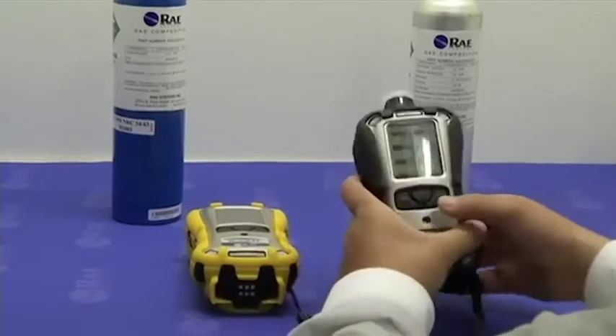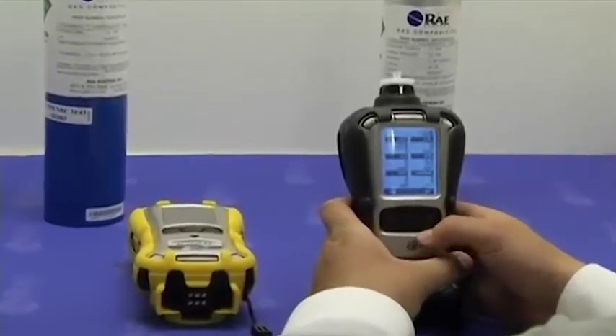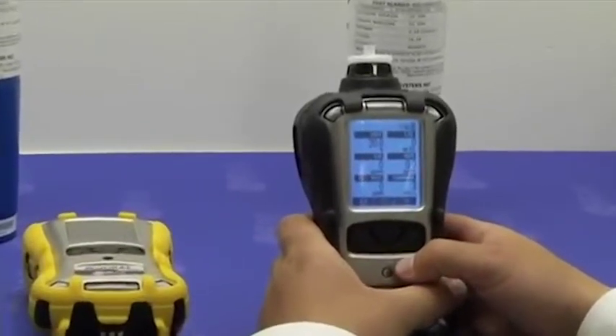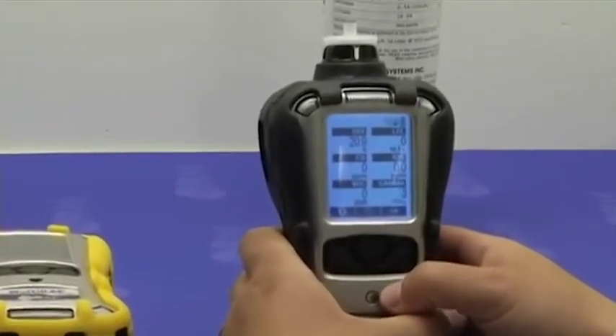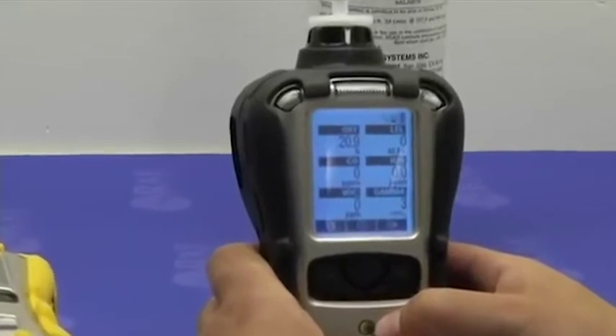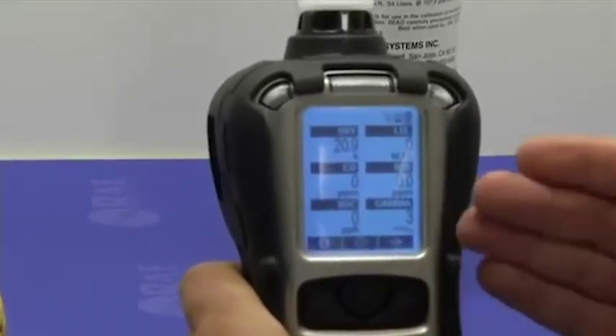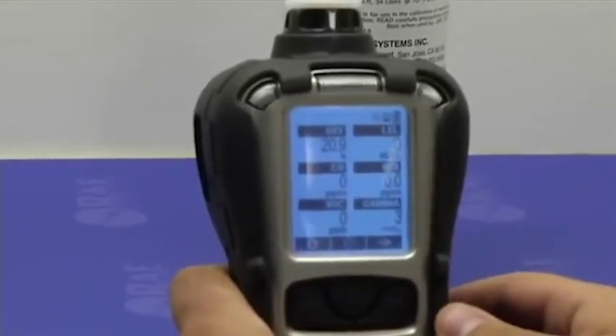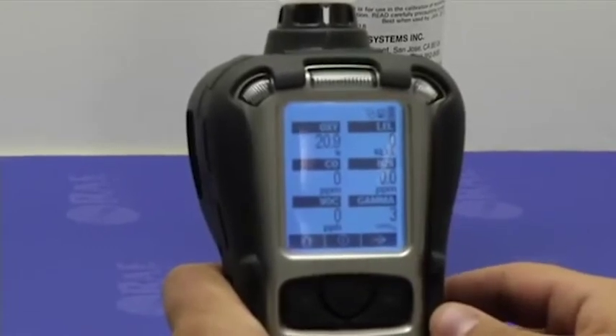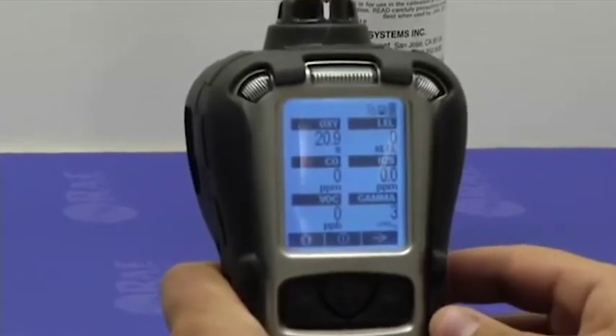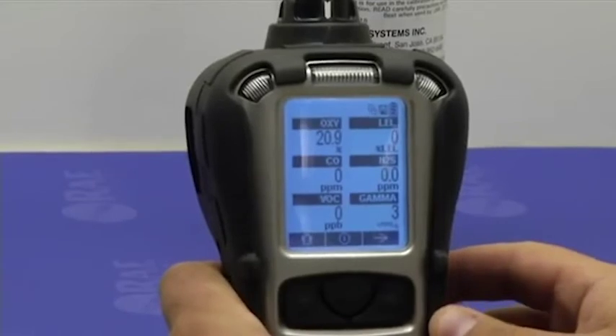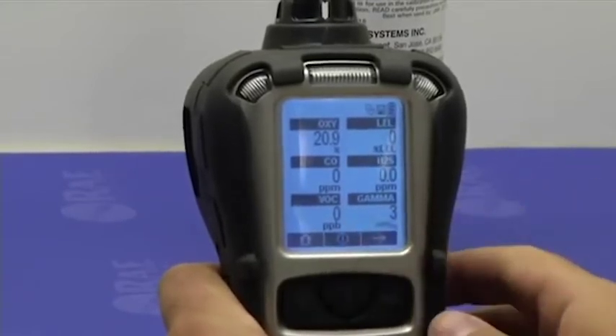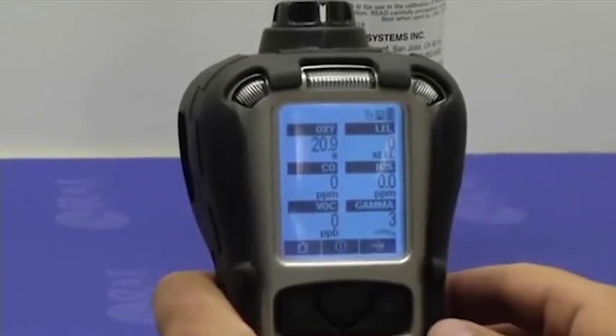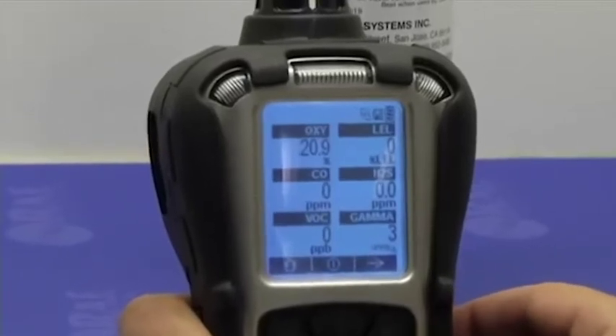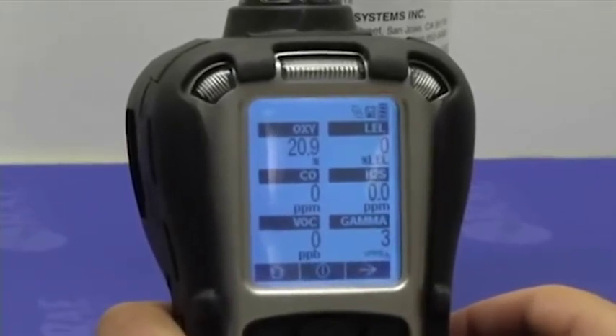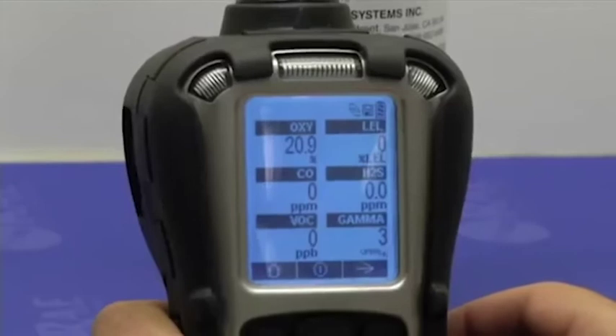Depending upon the configuration of the MultiRAE that you have, you may or may not be able to bump all the sensors at the same time using one gas mix. On this instrument, for example, we have 4 sensors, oxygen, CO, H2S, and LEL, that can be bump tested at the same time, but we also have the PID sensor that we would have to use a different source of gas for. So therefore, our bump test process is going to go in 2 steps.